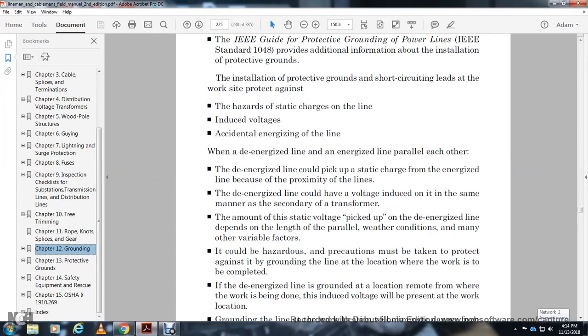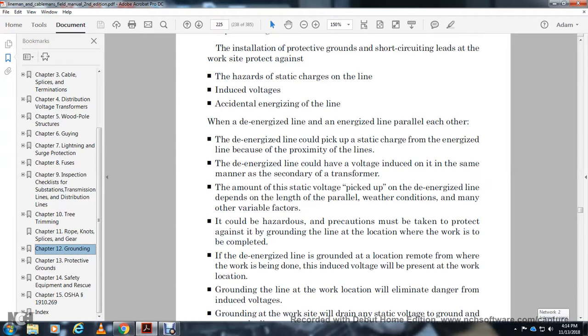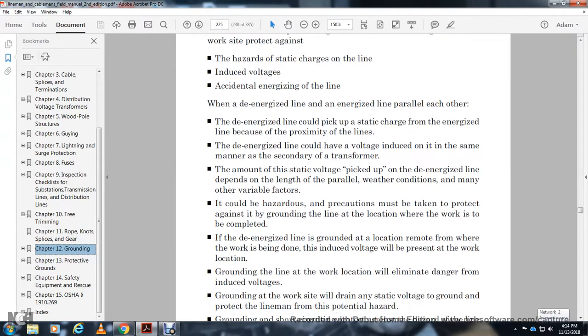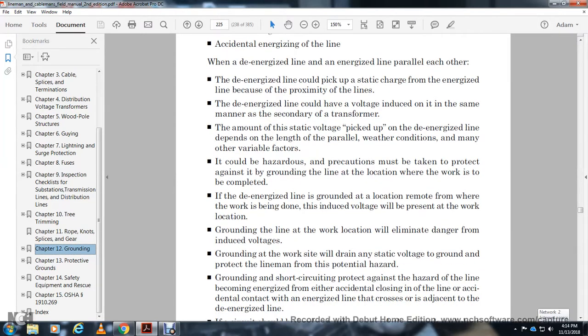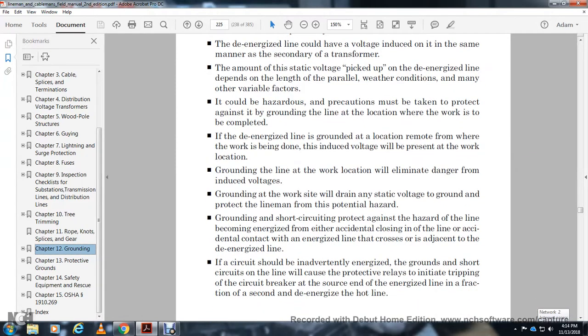Precautions must be taken to protect against this by grounding the line at the location where the work is to be completed. If the de-energized line is grounded at a location away from where the work is to be done, induced voltage will still be present at the work location. Grounding of the line at the work location will eliminate damage from the induced voltage. Grounding the work site will drain out any static voltage to the ground and protect the linemen from potential hazards. Grounding and short-circuiting will also protect against the hazard of the line becoming energized by accidental closing of the line, or accidental contact with an energized line crossing the de-energized line.